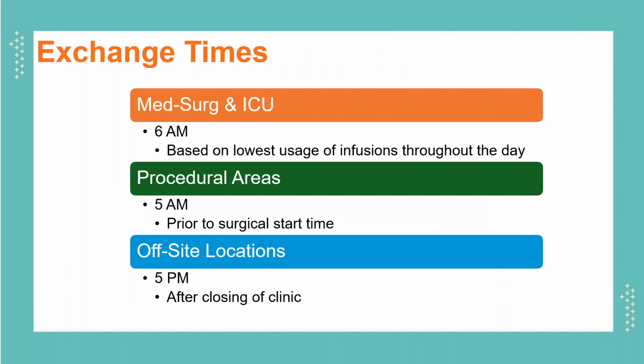During the planning phase, we thought, okay, so when is the best time to exchange these devices? And of course, it was going to be different based on the location. For inpatient spaces, med-surg and ICU, we identified that the best time to physically swap the devices was whenever the usage was at its lowest. Since our devices are integrated, we are able to look at data and see how many pumps are infusing at any given time. So we did see daily trends, and 6 a.m. was among the lowest times of the day, where if we exchange the device then, we would have fewer issues with ongoing infusions, and most of our pumps would be available for a quick swap.